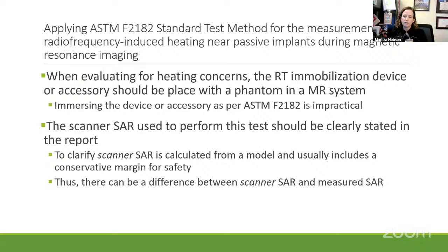To clarify, scanner SAR is calculated from a model and usually includes a conservative margin for safety. Thus, there can be a difference between the scanner SAR and your measured SAR. That's why it's important to have indicated on that report what SAR it's stating, so you are sure it's adequate for your MRI system.